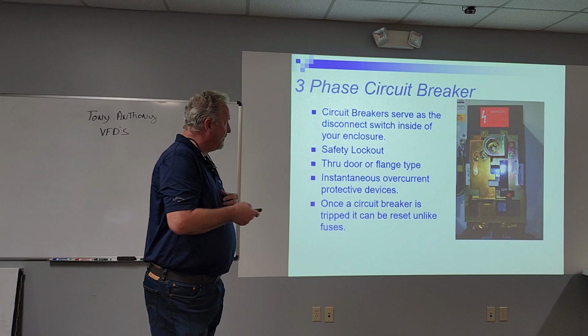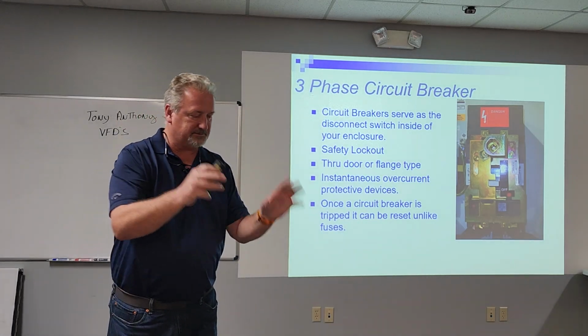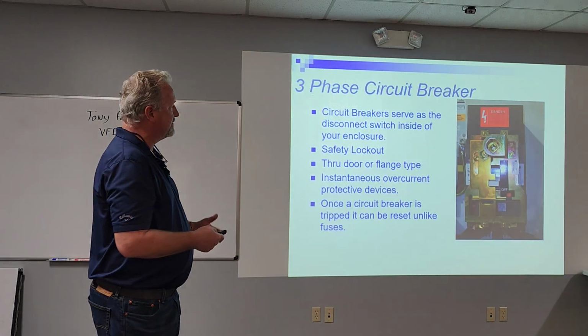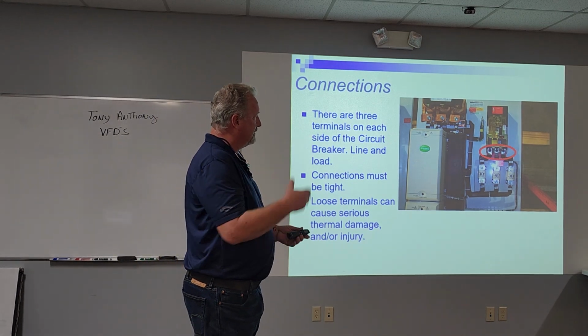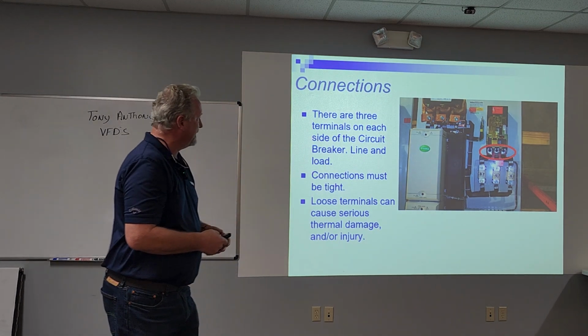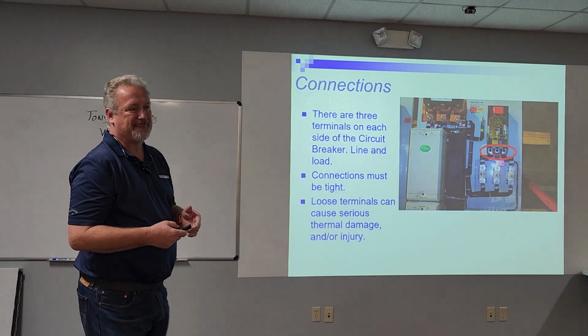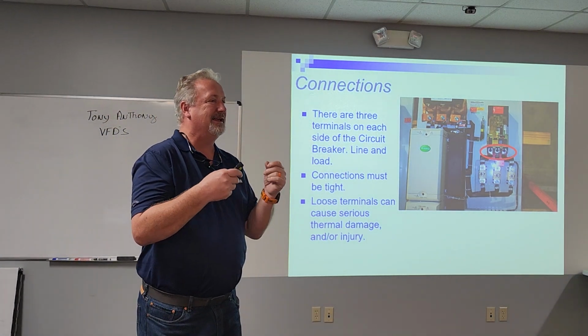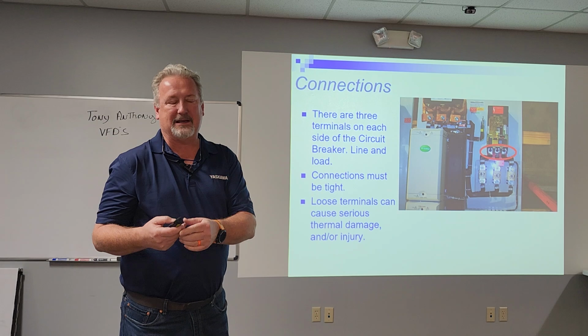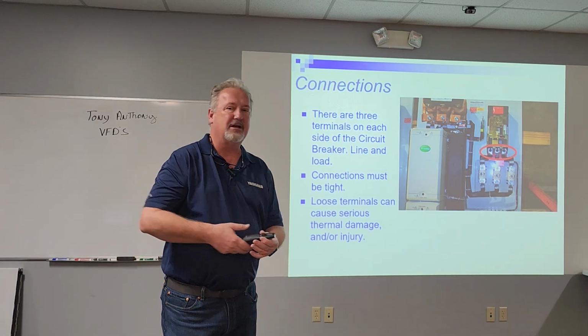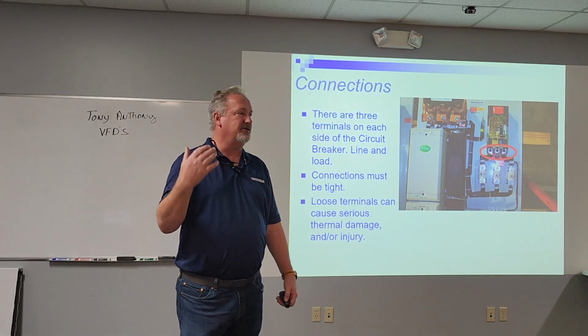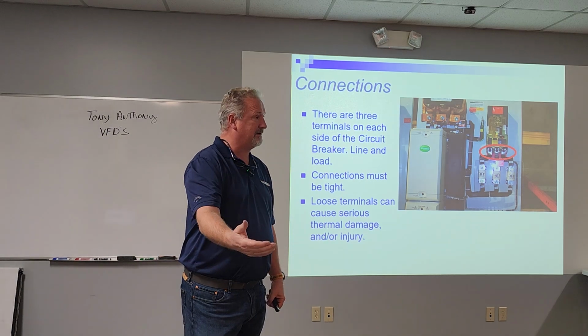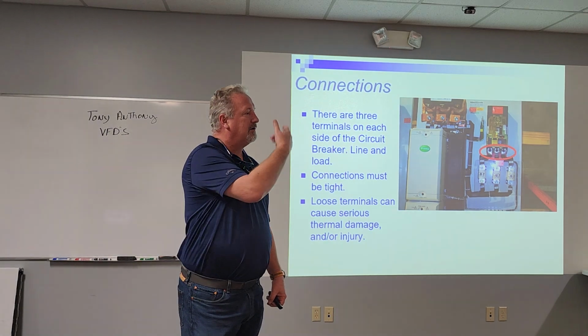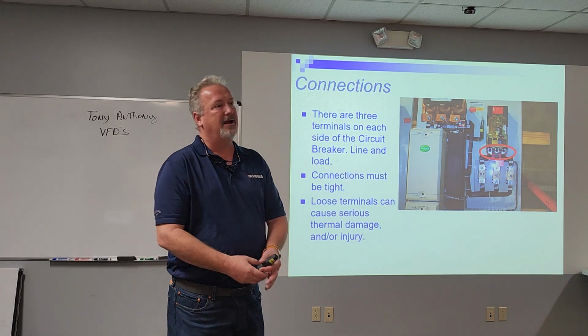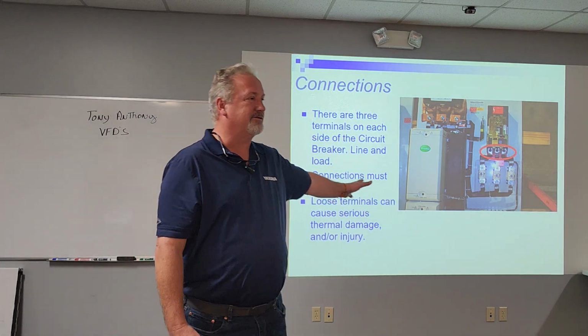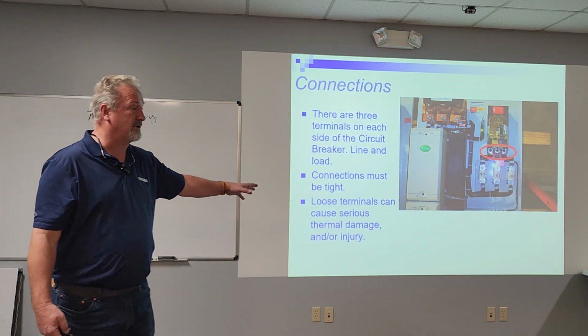Connections. Go back to the breaker. We're feeding power in. Power's coming out of the bottom of the breaker. Power's coming into the drive. It's going to connect to the drive through some terminal or something somewhere. The big thing about connections is always, with any electronic equipment, I don't care if it's switchgear, electrical, anything that has electricity, when you go back to do maintenance or a checkup a year or two later, retorque your connections. One of the leading causes of drive failures and most electronic failures is loose connections.